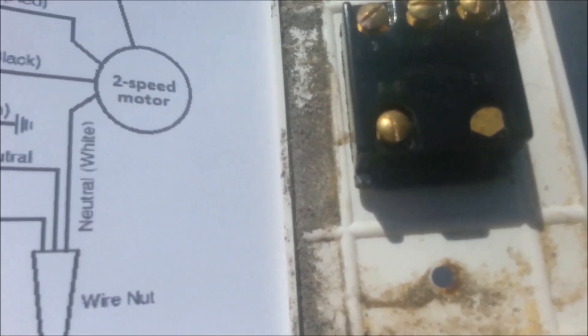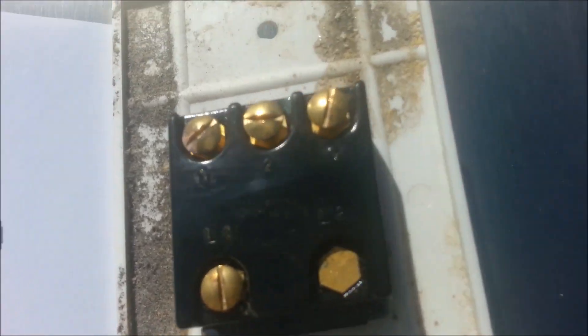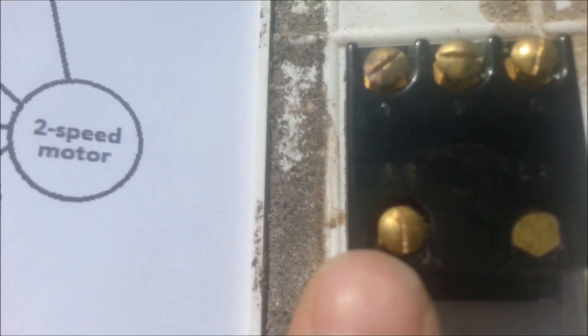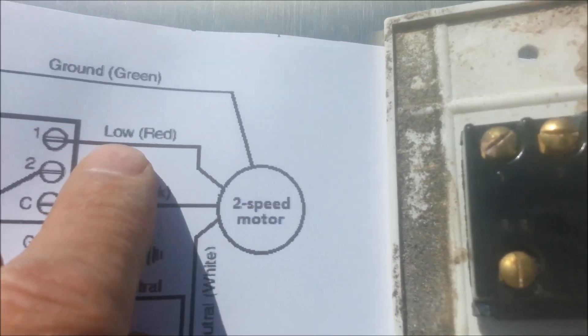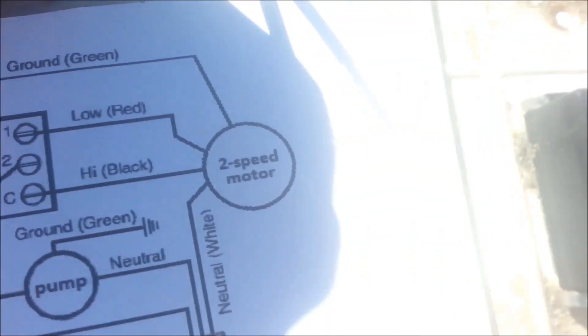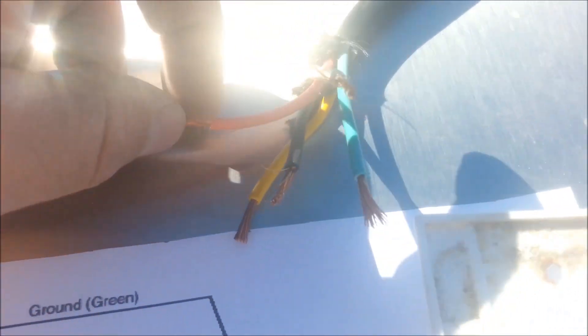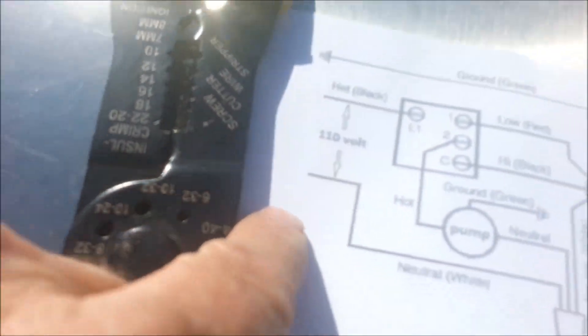So make sure you follow your own schematics, it's only for this. So right here is L1, that's going to be where the hot's coming in. So then we got low, red. So red is going to be for low speed on the motor. Black for high speed. Ground is just going to go straight to ground. And white is going to go straight to the white coming in off the wall, right here.